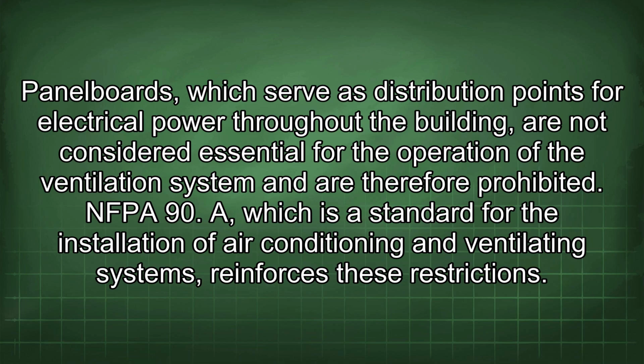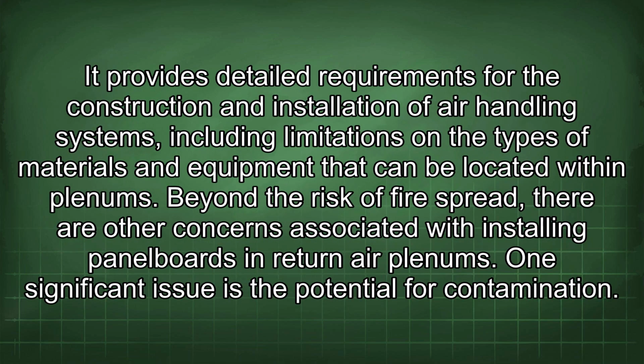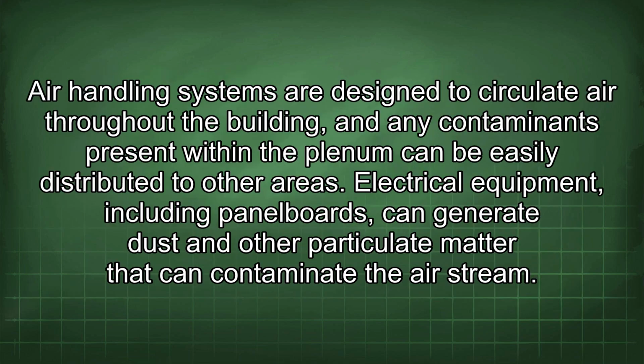NFPA 90A, which is a standard for the installation of air conditioning and ventilating systems, reinforces these restrictions. It provides detailed requirements for the construction and installation of air handling systems, including limitations on the types of materials and equipment that can be located within plenums. Beyond the risk of fire spread, there are other concerns associated with installing panelboards in return air plenums. One significant issue is the potential for contamination. Air handling systems are designed to circulate air throughout the building, and any contaminants present within the plenum can be easily distributed to other areas.